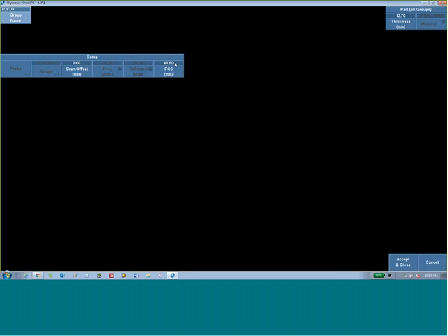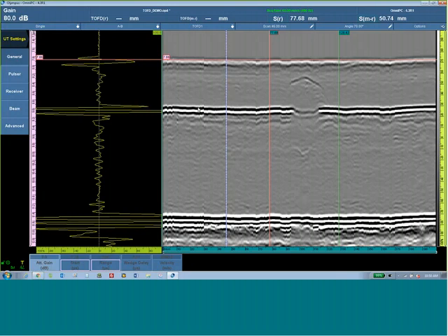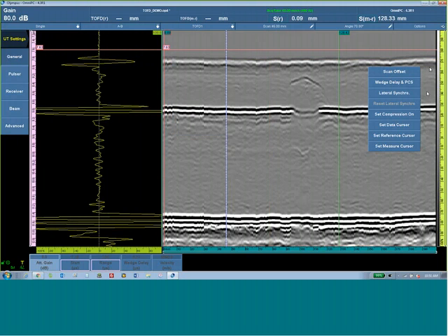If I don't know the real thickness of the pipe, I can't recalculate the PCS with a nominal thickness. Use of a nominal pipe thickness of an unknown pipe has no value in increasing the precision of the inspection. So my first function is to straighten this lateral wave.